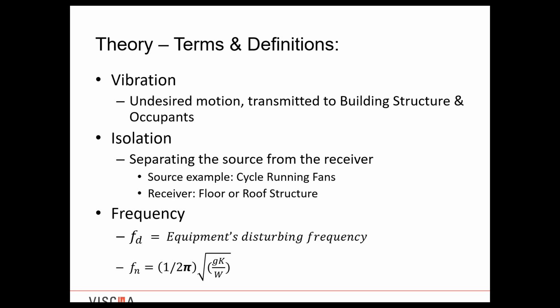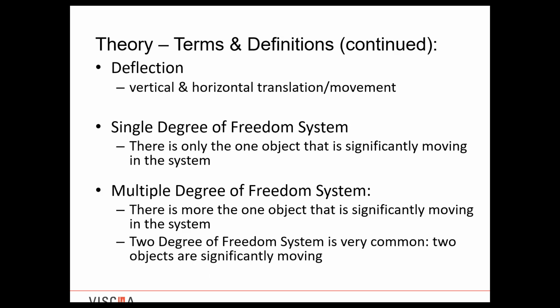And again, that isolation in our industry is often a spring isolator. It can be an elastomeric material such as neoprene or natural rubber. And, as John mentioned, if you take it to the far extreme, if you get wood to deflect a little bit, then yes, you're providing a tiny bit of isolation. So when we talk in terms of frequency, this F sub D is the equipment's disturbing, or you'll hear people call it driving, frequency. And the F sub N is the natural frequency of the material, the substructure, and that formula is 1 over 2 pi times the square root of gravity times your spring constant in the numerator over the weight in the denominator. And we'll see later that you can have that in different terms of the variables.